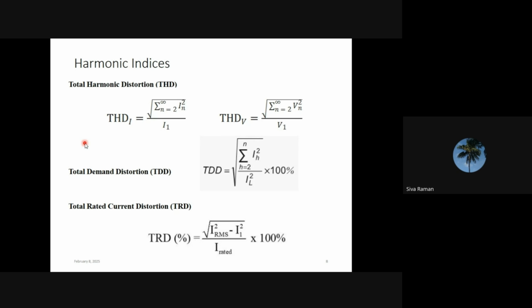So consider a scenario. Totally 10 customers are connected to the common electrical grid. Nine customers have controlled their harmonics, and only one customer is injecting harmonics into the system. So the other 9 customers also get affected. In this case, the company maintaining the electric power system has to penalize the customer which is producing the harmonics, right? So for that reason, we have harmonic indices or harmonic evaluation methods.